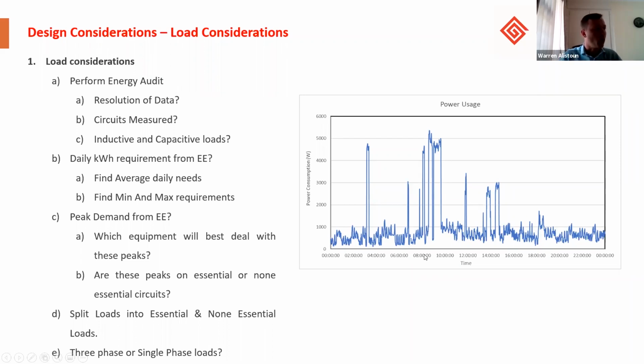So when performing an energy audit, we need to understand the resolution of the data. Most data loggers used in the field give a resolution of 1 hour. That can be quite challenging in terms of understanding the load, because with 1 hour resolution data, a peak like this one here will average out to less than 3 kilowatts. And if this is put onto the backup circuits of the inverter, which say is restricted to 3 kilowatts, we'll have overloading problems. So I always recommend using a product which can monitor the voltage, current, and power factor at least in 1 minute intervals, at best 1 second.